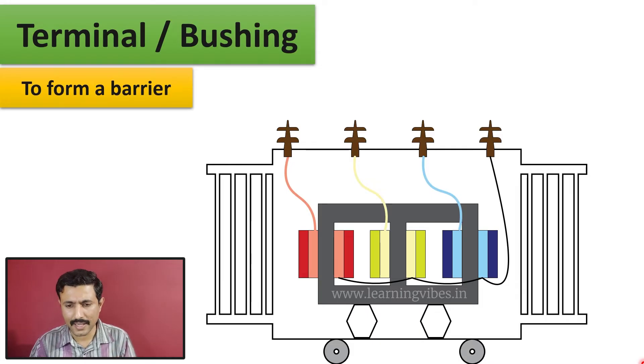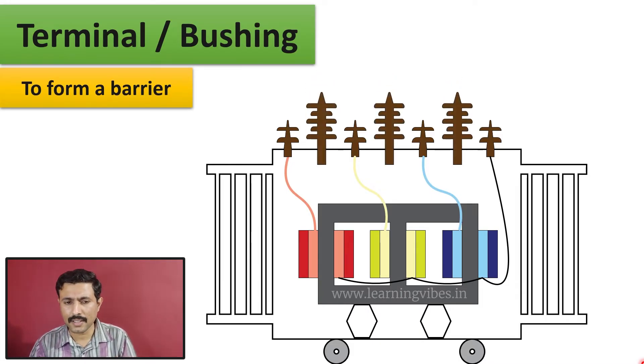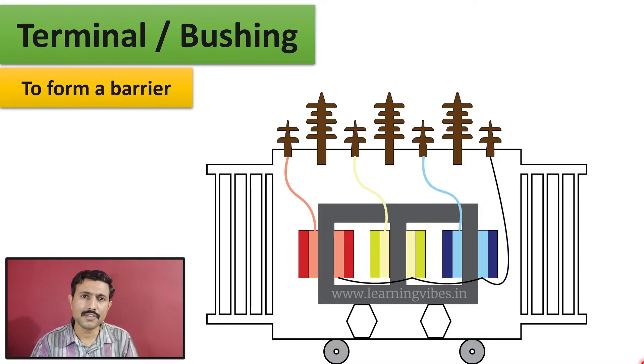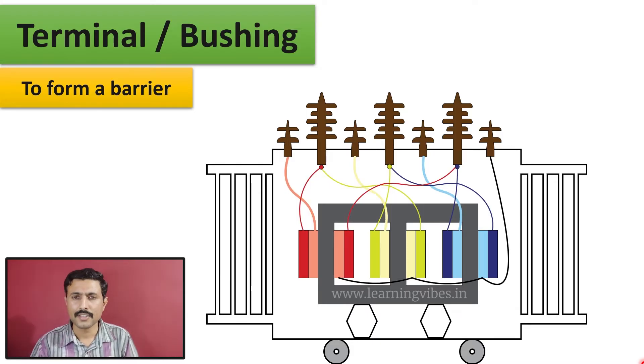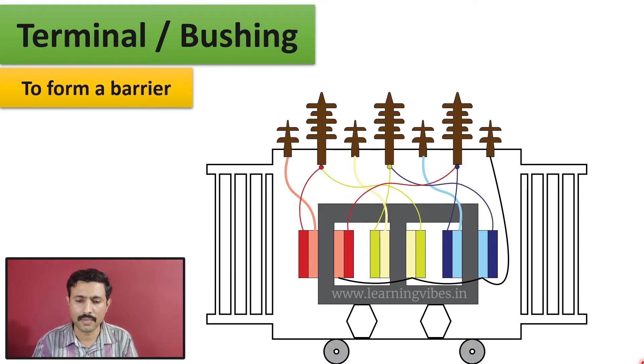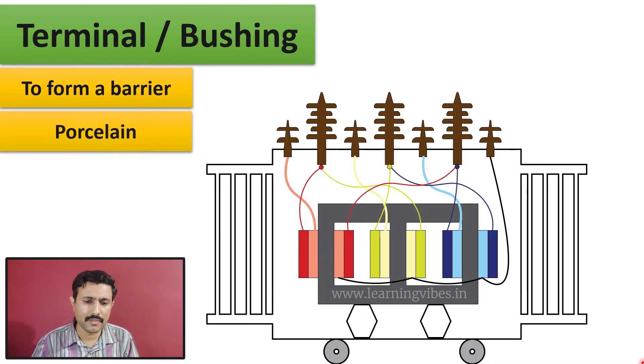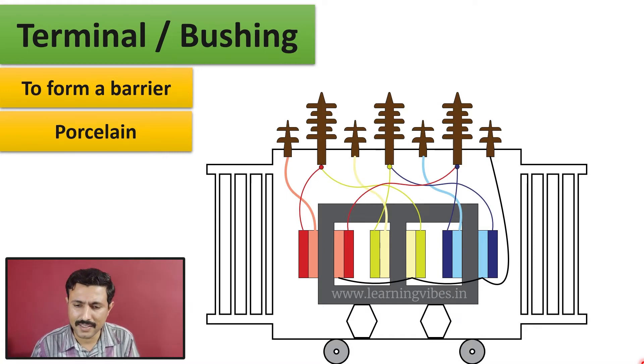On the high voltage side, the high voltage terminals or bushings are a little larger because of the higher voltage level. The connection of HV is in delta. R and Y are clubbed together and create R phase; Y and B club together and create Y phase; B and R club together and create B phase — this is how the R, Y, B delta connection is formed. These bushings are made up of porcelain material or epoxy resin.